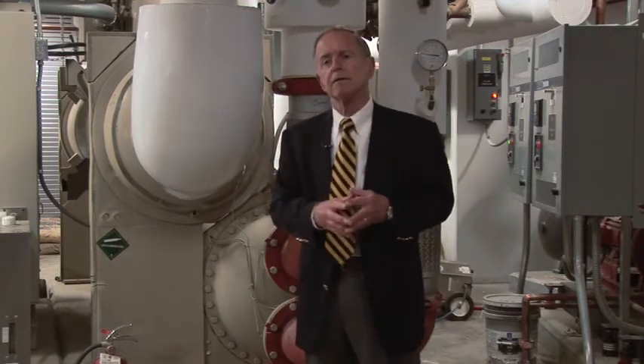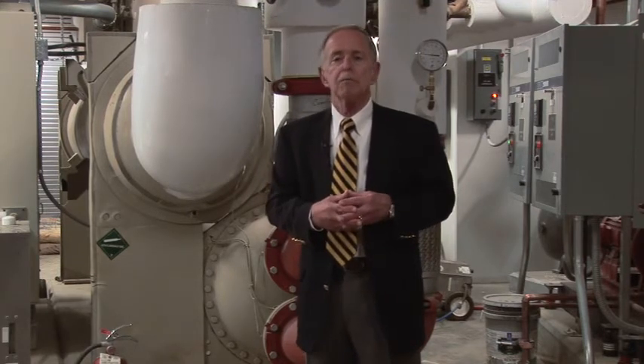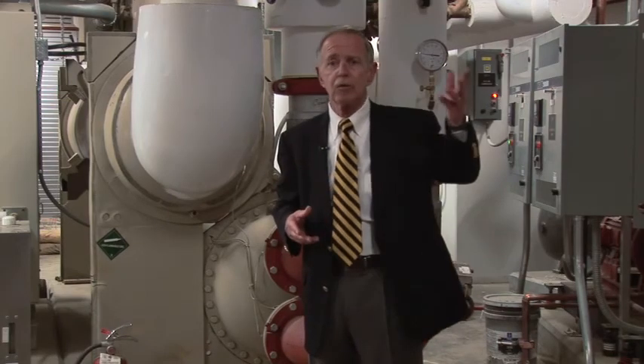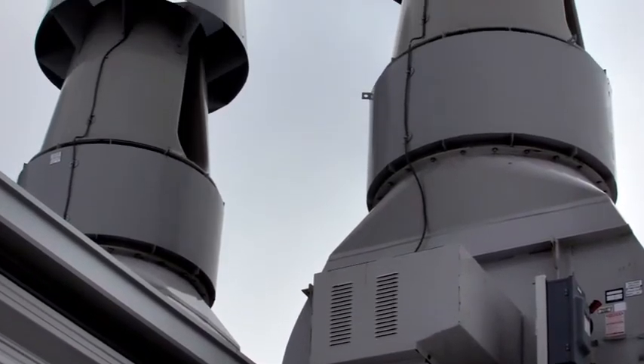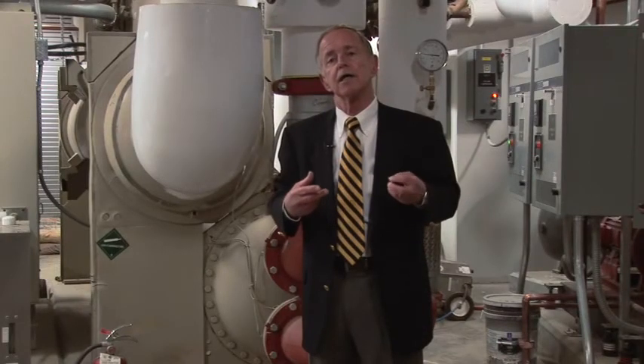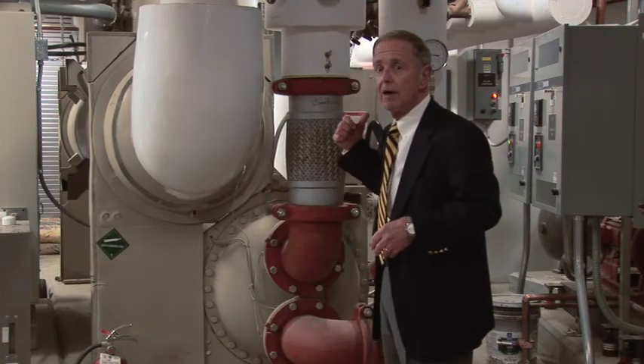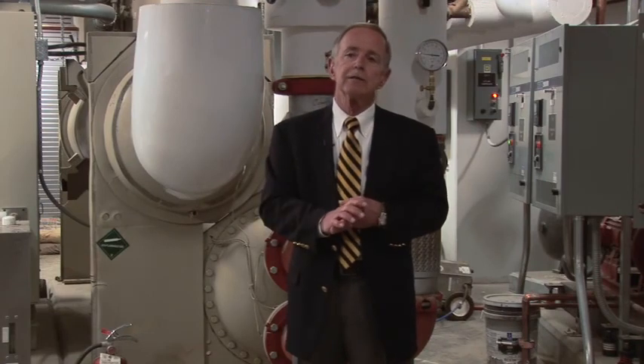When we do that, we find that the evaporation of the water in the cooling tower, the blow-off of that cooling tower, equals about 1.3 gallons a minute on a typical summer day. And guess what we're manufacturing on the other side when we got that condensate water in the first place? The system will generate 1.3 gallons per minute in the process of generating this condensate water. So essentially, we're manufacturing water over here, and we're using it over here to make up for the evaporation and the blow-off of the cooling tower. We'll talk more about the heating system when we get to the labs, which will be next.